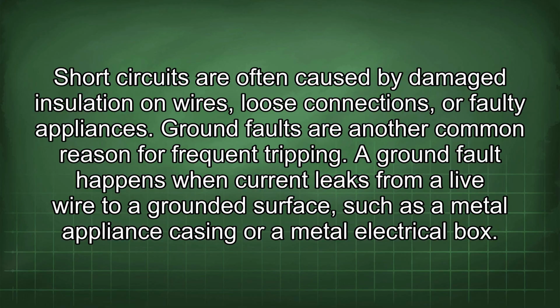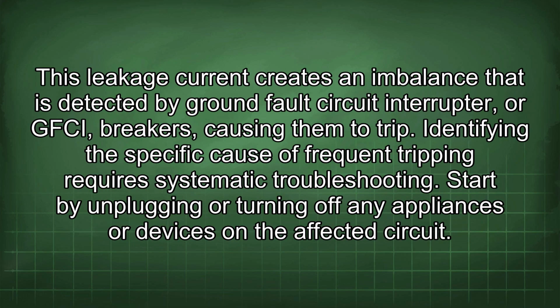Ground faults are another common reason for frequent tripping. A ground fault happens when current leaks from a live wire to a grounded surface, such as a metal appliance casing or a metal electrical box. This leakage current creates an imbalance that is detected by ground fault circuit interrupter, or GFCI, breakers, causing them to trip. Identifying the specific cause of frequent tripping requires systematic troubleshooting.